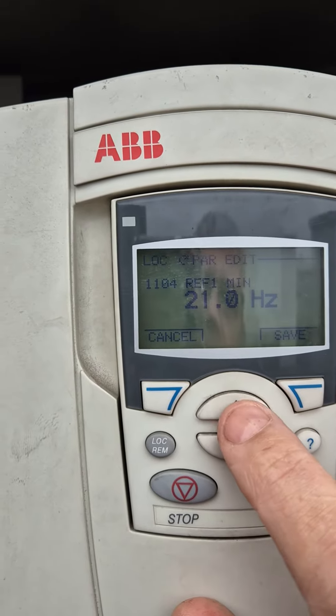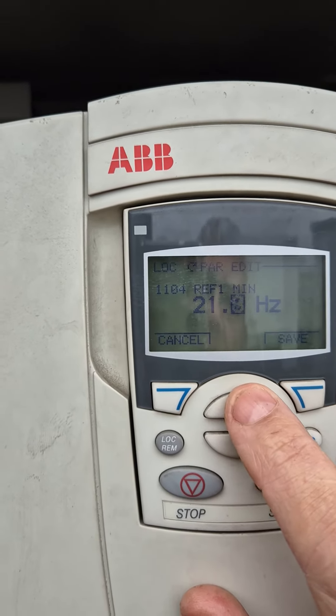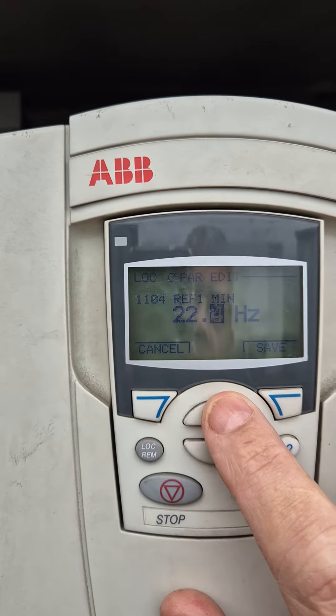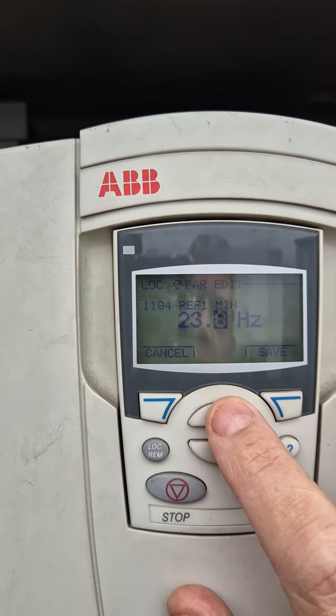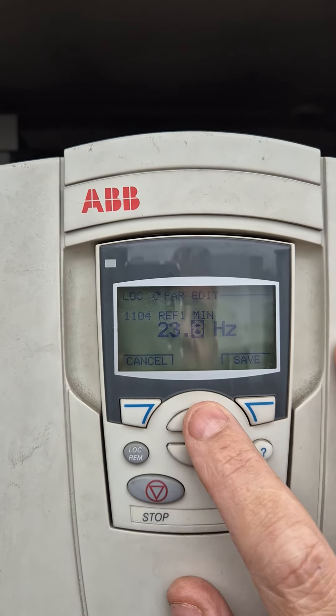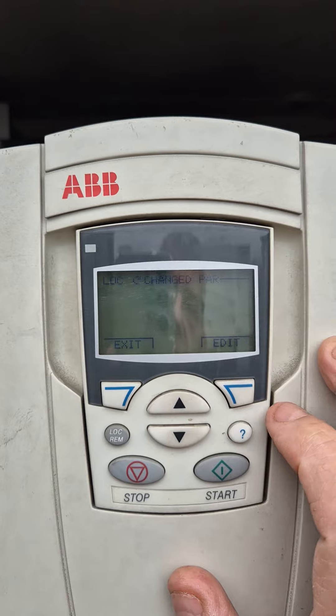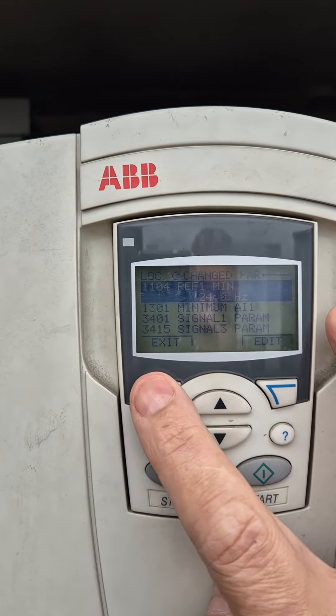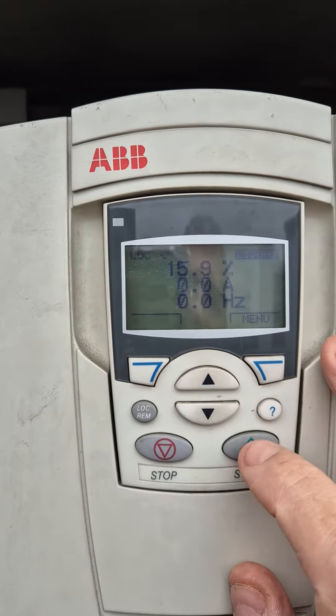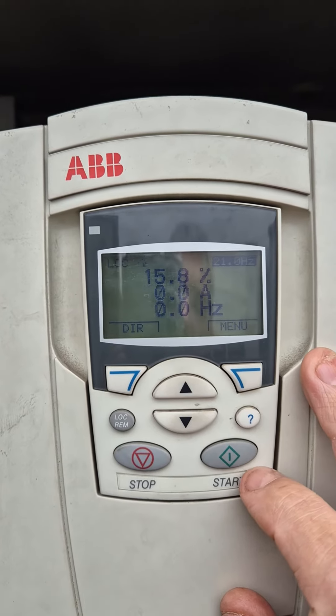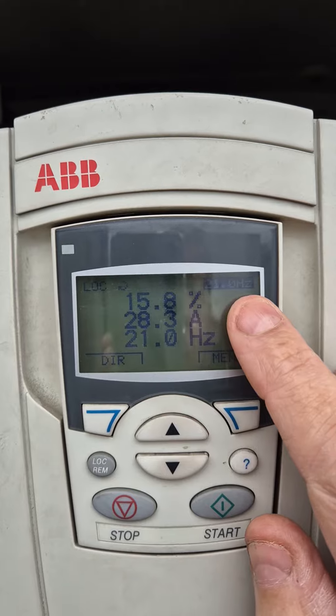Use the up and down buttons to bring it up to how fast you want it to run. Don't go too fast because you don't want the water coming back down to the chillers too cold. Bring it up to 24 Hertz, press save, then exit. When you press start you'll hear them start up — they're now running at 24 Hertz.